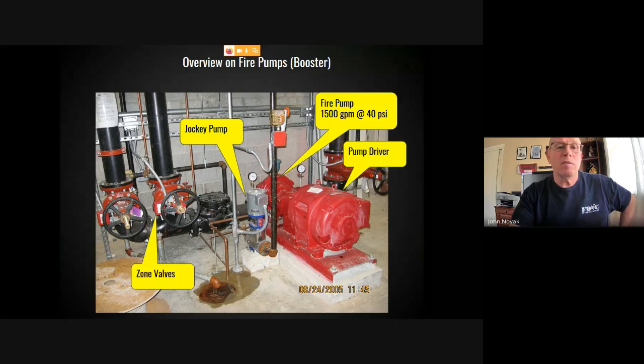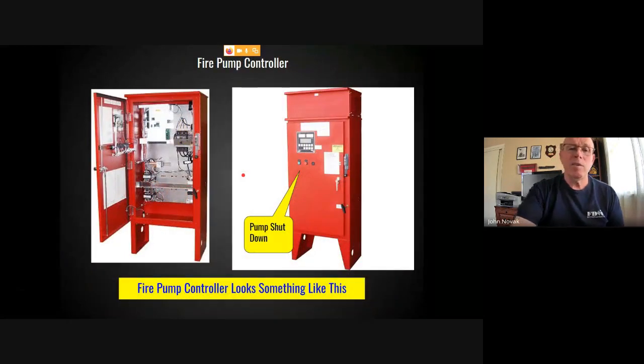Zone valves, again, OS and Y valves, outside stem and yoke. This valve is closed, we don't see any threads, and this valve is open, so we see the threads. And again, the length of the stem is going to give you the size of the pipe. So this appears to be a 6-inch sprinkler riser. And there's a fire pump controller. It's going to look something like this.